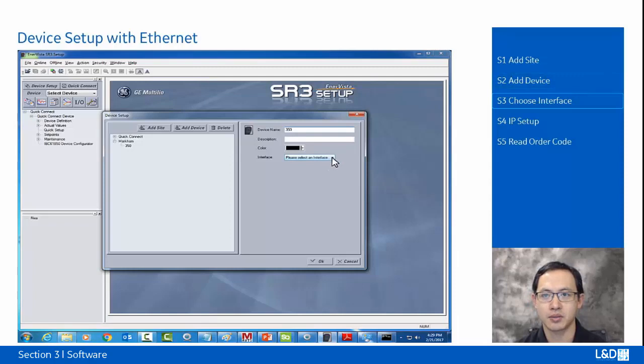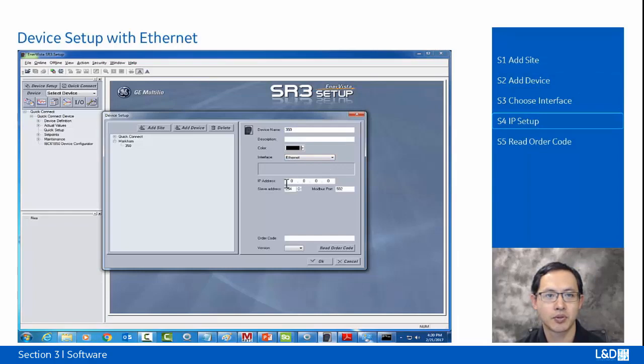And step 3 is to choose the interface to be Ethernet. And step 4 is to type in the IP address we just set up by using the USB port. Unless you change the default slave address and Modbus port, we're just using the default 254 and 502, and this setting can be verified by using the front panel or using the USB front panel connection. And the last step, step 5, is to click the Read Order Code button.